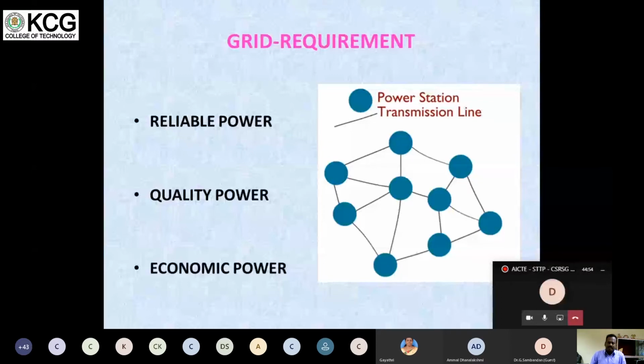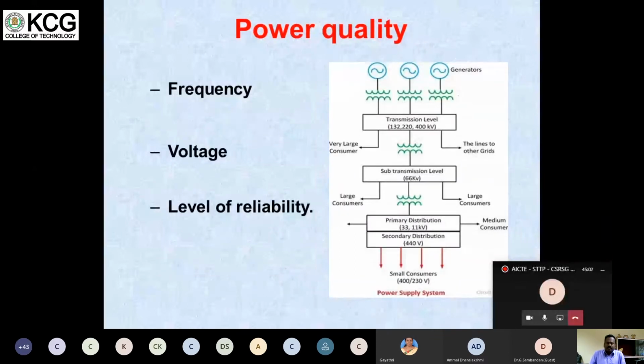This is our system. You can see there are power stations connected to transmission lines. This is what we say is our grid. That is why we discuss power quality, frequency, voltage, and level of reliability. In all places, for example if we take 230 volt, 440 volt, some deviation is allowed. This deviation is normally plus or minus 6%. That is the minimum allowed. The voltage supplied should be within this 6% limit only. When we go for higher voltage, on the lower side we allow minus 10%, on the higher side we allow 10 to 12%.